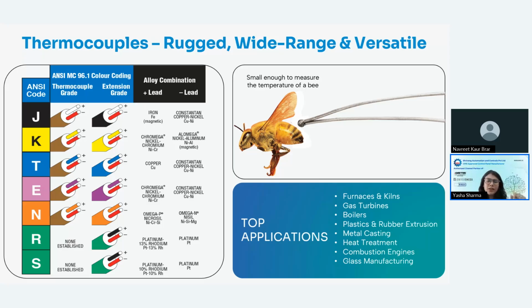Sometimes I wonder that a thermocouple can be made small enough to measure the temperature of a bee, as you can see on the slide. K type is one of the most widely used thermocouples in industrial processes. J type, K type, all these are very useful in the applications I have mentioned, like furnaces and kilns, gas turbines, boilers, plastic and rubber extrusion, metal casting. These are all very high temperature processes, and these thermocouples find use in heat treatment, combustion engines, and glass manufacturing industries.